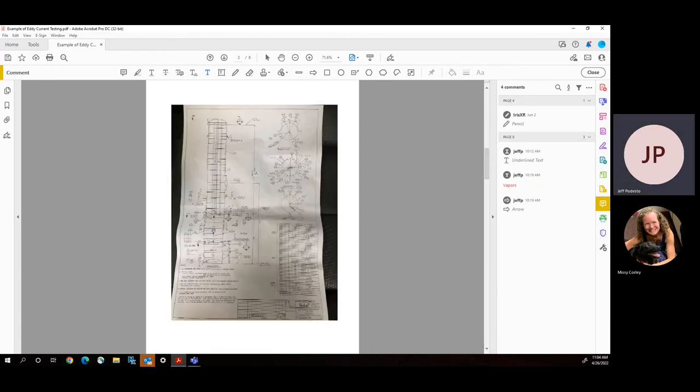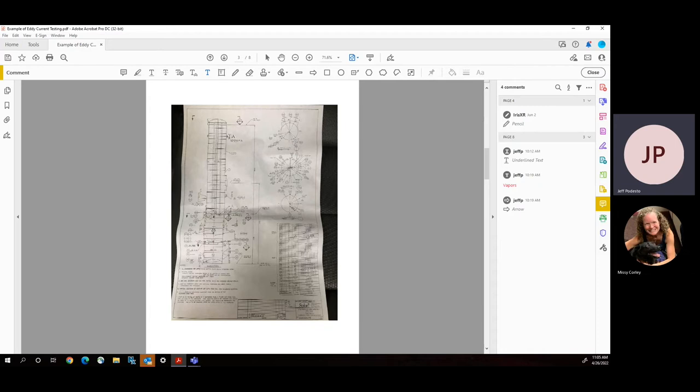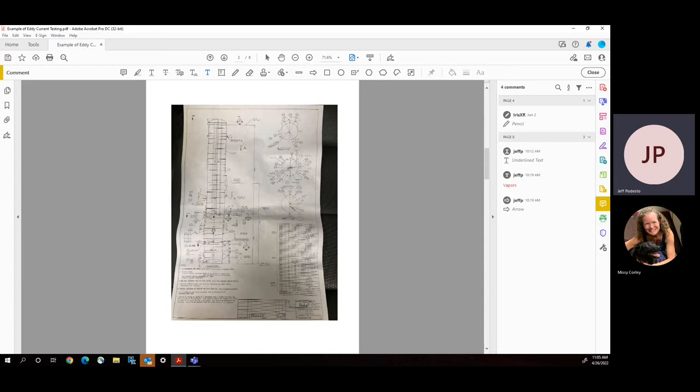We make sure to analyze the existing evaporator to know where all the entry points are, where vapors are coming in, where vapors are leaving, where condensate should drain out. So, we make sure that we understand the piece of equipment thoroughly because the feedback that we get from the test, along with where all of these inlets and outlets are to each one of the evaporators, helps us make a decision on what's going on.